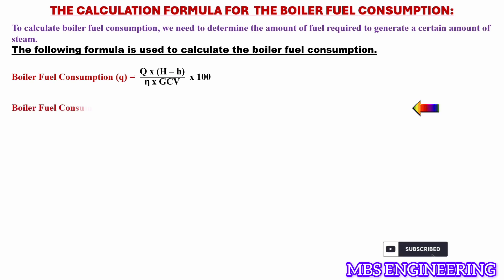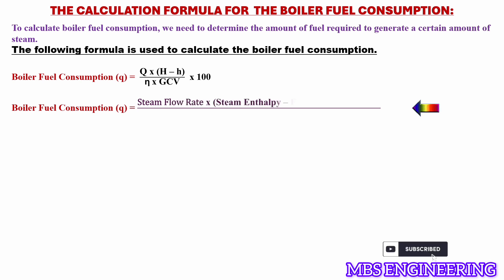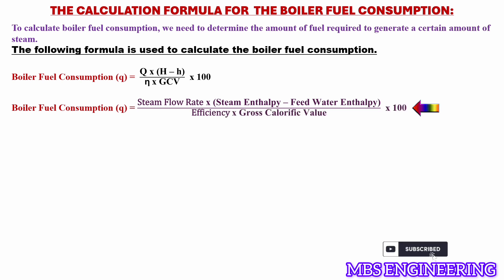Or, the boiler fuel consumption q is: the steam flow rate multiplied by (steam enthalpy minus feed water enthalpy), multiplied by 100, and then the obtained value is divided by the boiler efficiency multiplied by the fuel gross calorific value.